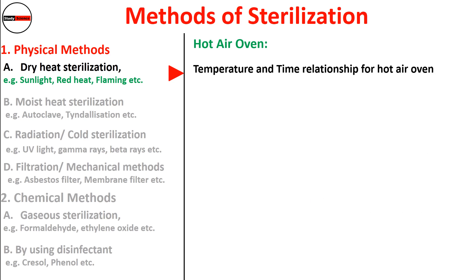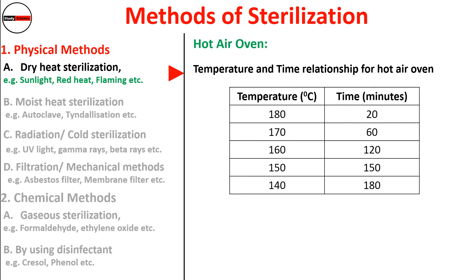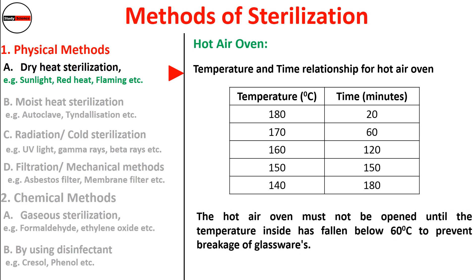The temperature-time relationship for the hot air oven is: 180°C for 20 minutes, 170°C for 60 minutes, 160°C for 120 minutes, 150°C for 150 minutes, and 140°C for 180 minutes. The hot air oven must not be opened until the temperature inside has fallen below 60°C to prevent breakage of glassware — this precaution must be taken when sterilizing glass articles.